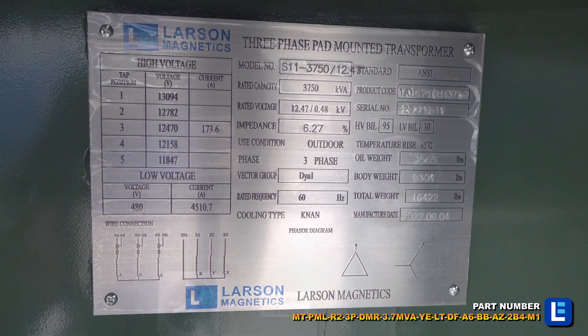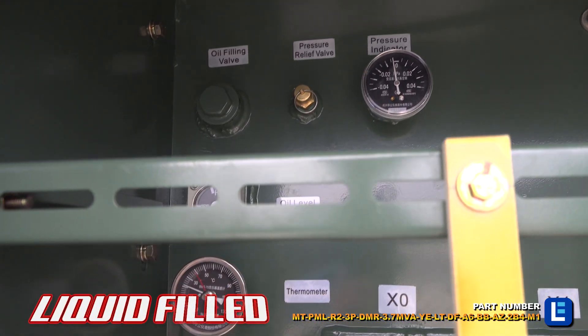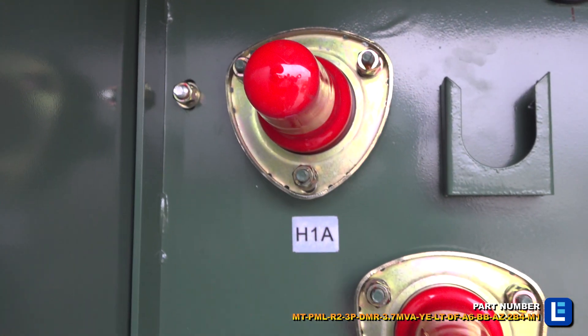An enclosed design caters to installations on concrete pads without protective fencing. This transformer has a primary loop feed for single installations and dead front primary connections. It also features a five position tap changer to allow small changes for voltage. There are no load break switches, rapid rise relays, and protection fuses present on the system.